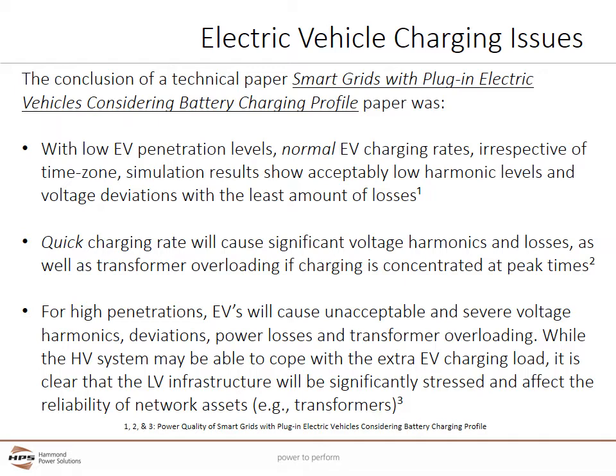This is becoming a much larger issue as more and more level 3 fast charging stations with very high power loads are installed. For high electric vehicle penetrations, which is where North America is heading right now, EVs will cause unacceptable and severe voltage harmonics, deviations, power losses, and transformer overloading. While the high voltage systems may be able to cope with the extra EV charging load, it is clear that the low voltage infrastructure will be significantly stressed and affect the reliability of network assets, including transformers. This is why it is very important to understand the long-term issues and specify the proper transformers for these EV installations.